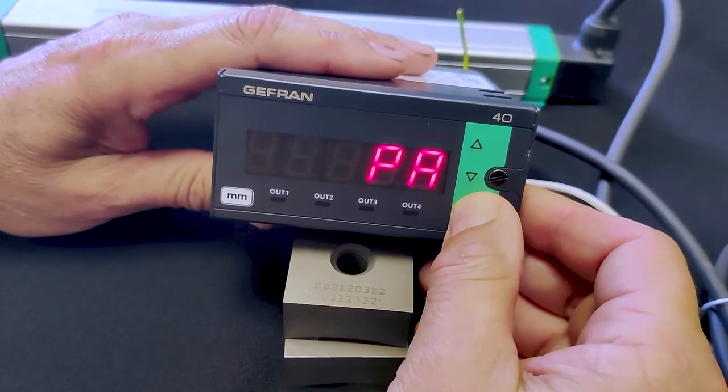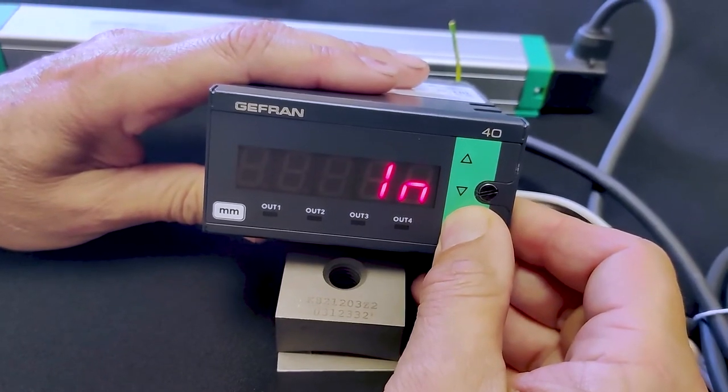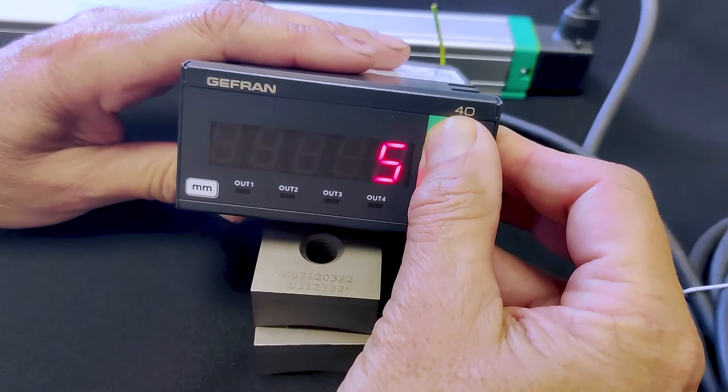To get to the user calibration you press and hold on the F key until you reach PA, which stands for password. The default password is 99.